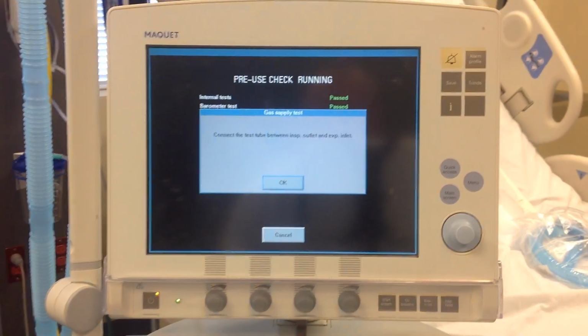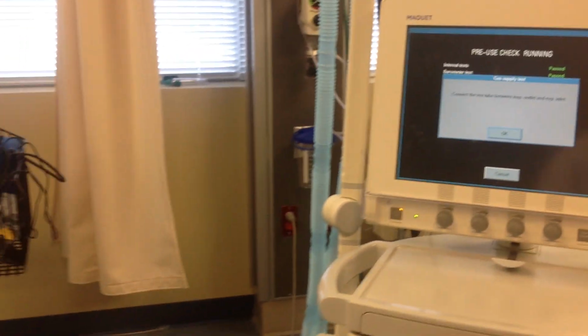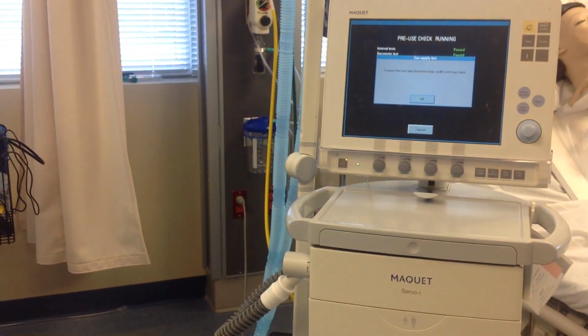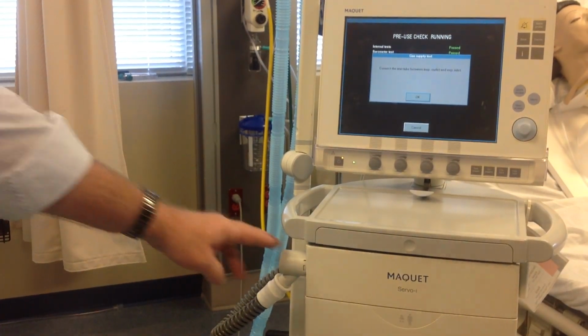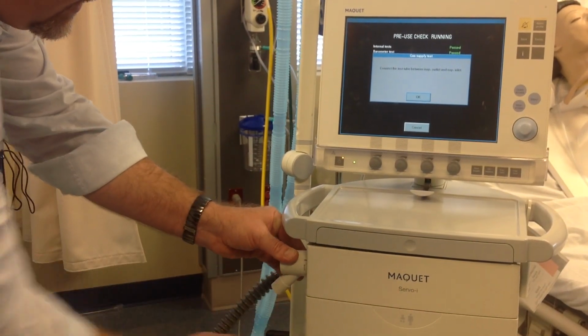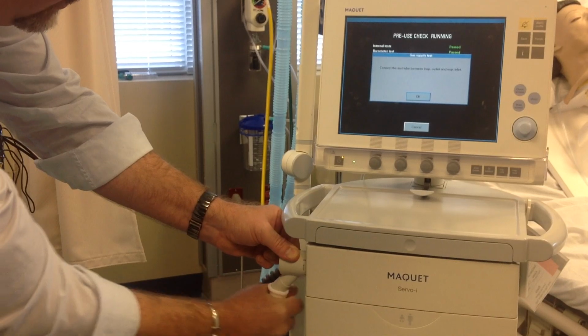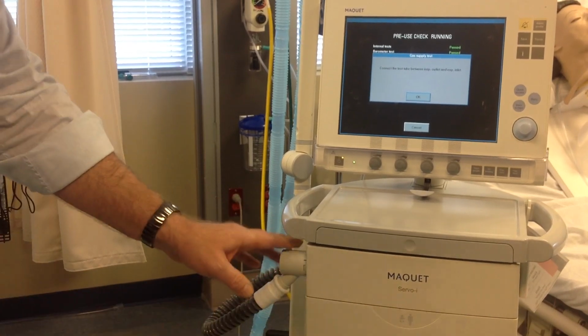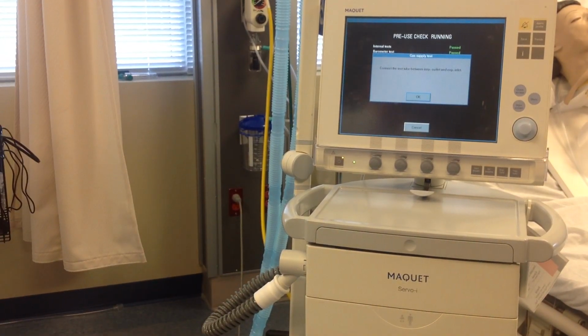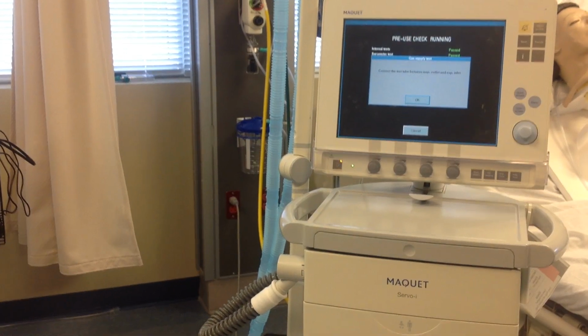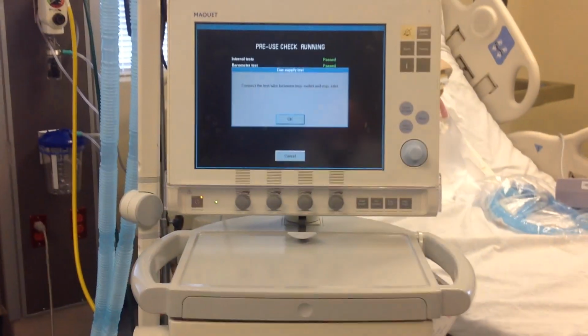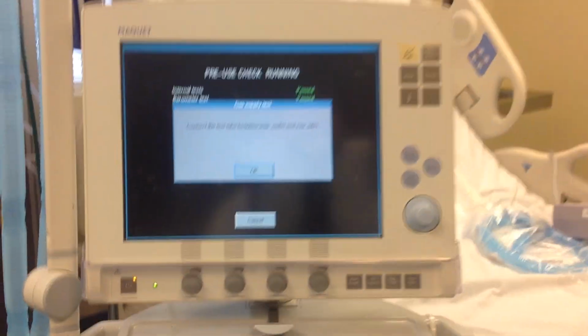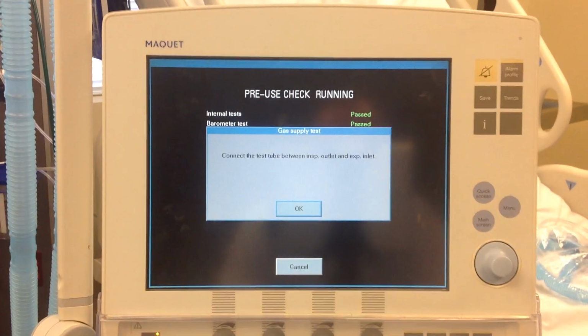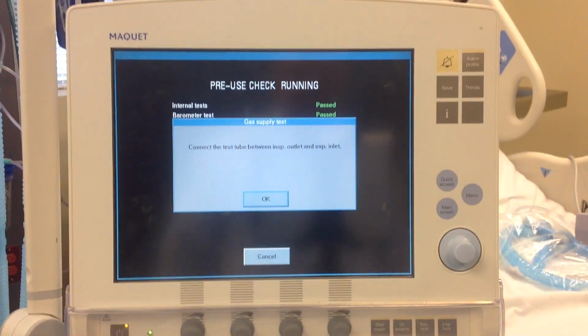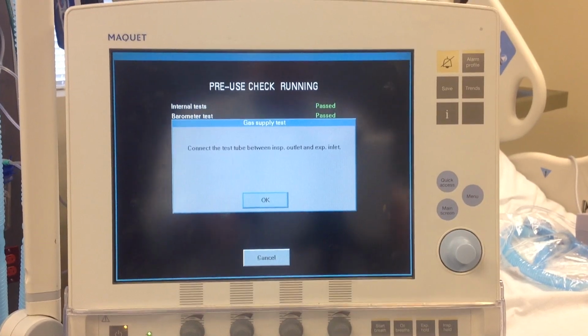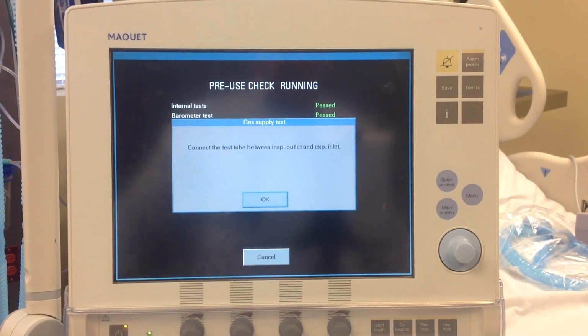We want to support this right here. So when I put this on, I am supporting it here. The reason being is when you do your pressure check, if you do not support that, you could form microfractures. And when you get the microfracture, it will not pass the pressure test. That was not an earthquake.